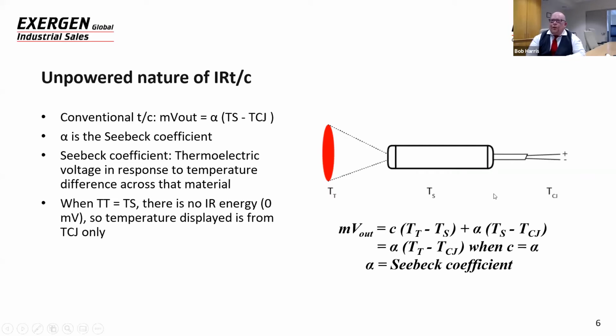So the only thing measured in the readout will be the temperature from the cold junction only. What we do is we calibrate these sensors so that C, the calibration coefficient, equals alpha, so that the millivolt signal out is equal to alpha times the temperature of the target minus the temperature of the cold junction. That way you can plug this IRTC into any conventional readout device that will measure a thermocouple. The IRTCs are also built with conventional thermocouple wire so that you can also use the cold junction compensation that's often used in these thermocouple readout devices. Next slide.